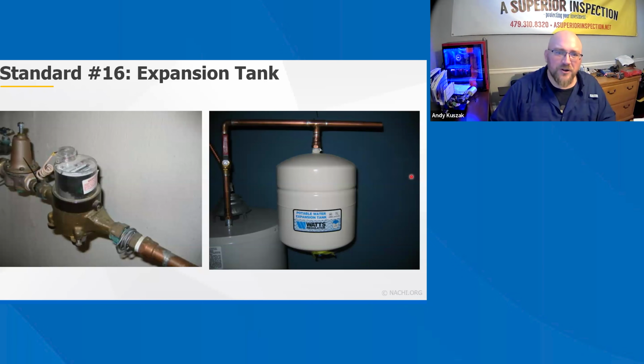So keep that in mind when you're inspecting a water heater. You might have other systems on there, but this is what I come across most often. If you have a tankless water heater system and no hot water circulation pump, you don't need a thermal expansion tank or a thermal expansion device. But when you do introduce an item that will make the system a closed system, then you do have to introduce a thermal expansion device. I had a long fight with a plumber and a builder on that one, so I got very versed in that aspect. All right.